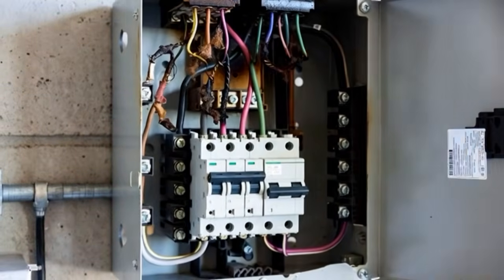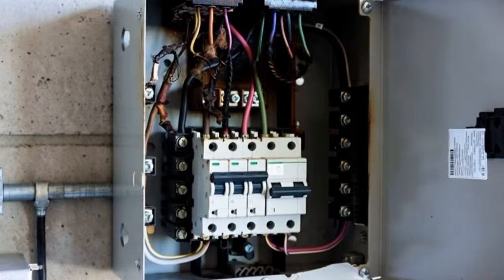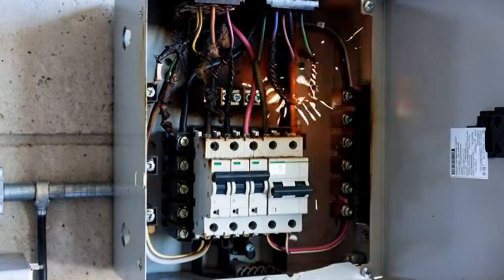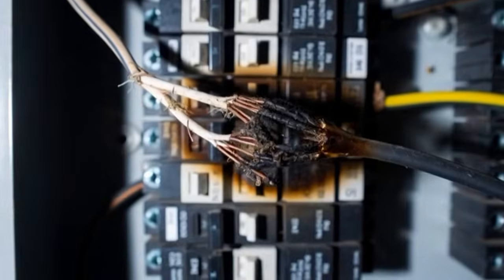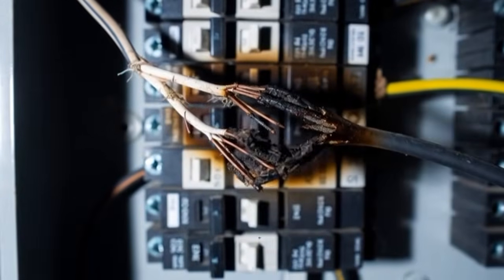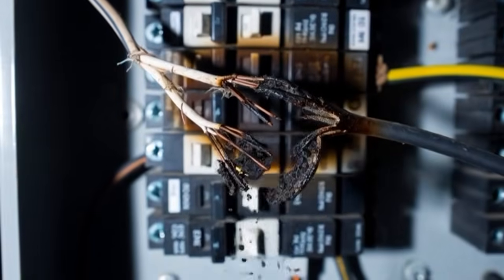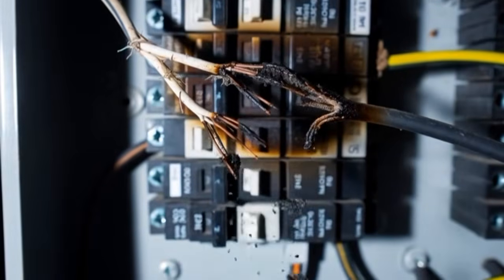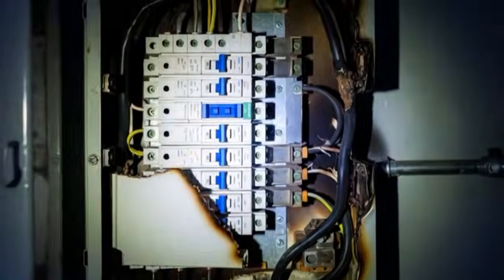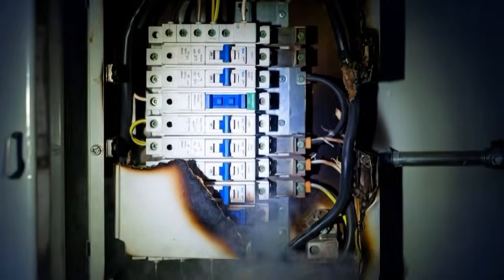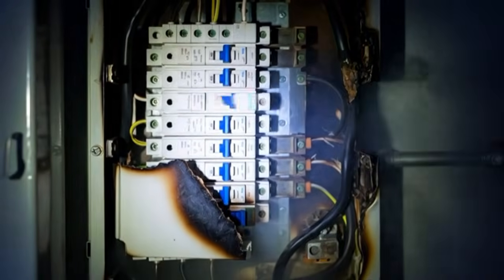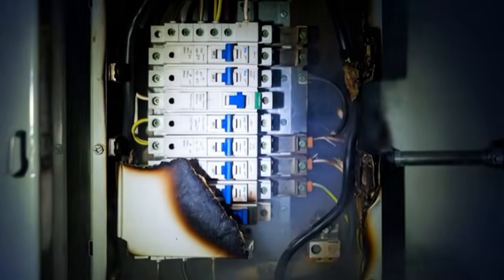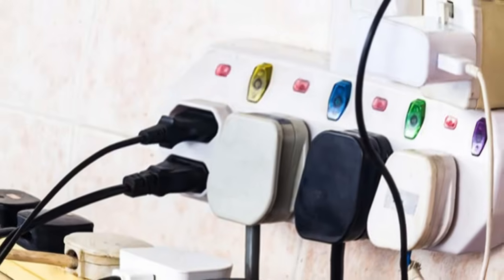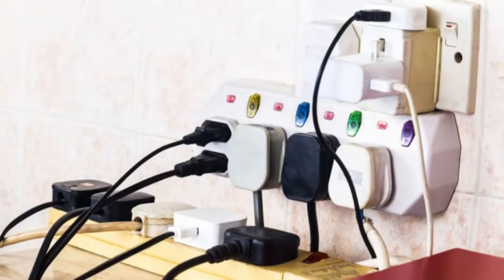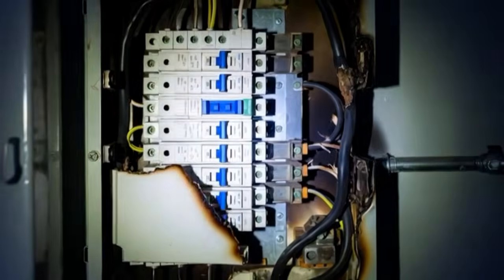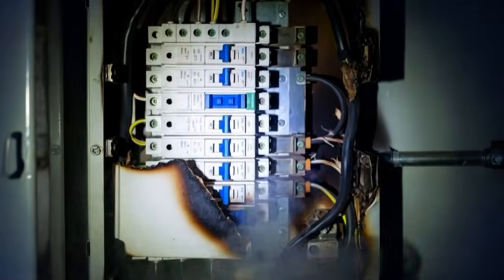Damaged wiring can create intermittent faults that prevent breakers from resetting. A wire with compromised insulation might arc to a nearby grounded surface. A loose connection might create enough resistance to trip the breaker under load. A backstabbed outlet connection might fail, and create a short inside the outlet box. These wiring problems are difficult to diagnose because they often hide inside walls and ceilings. The damage isn't visible from outside. The circuit might work fine for years until the damage progresses far enough to cause a fault.